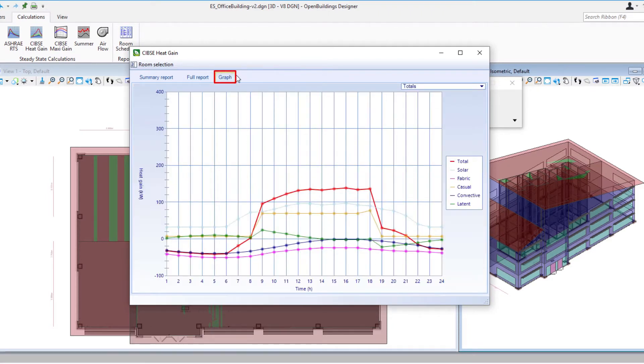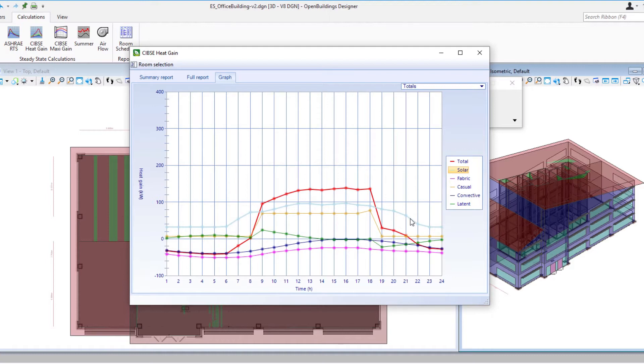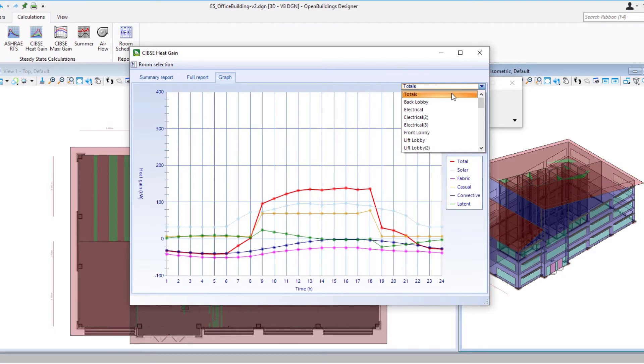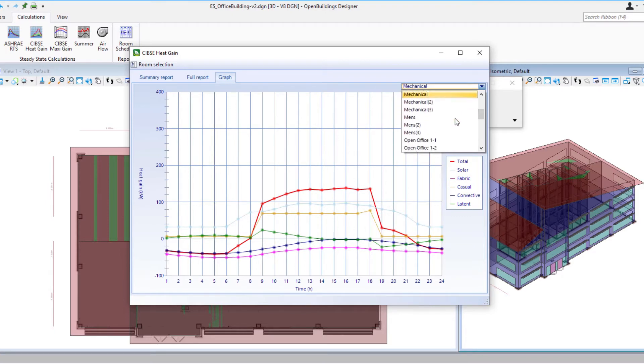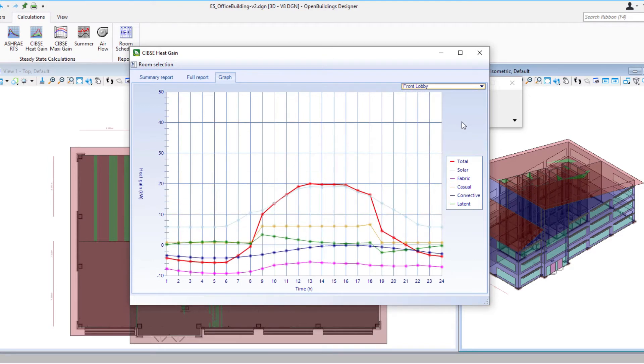And if we go to the graph tab it puts into a graph the different heat gains and we can see for instance that our solar heat gain is the greatest on our graph. Now that's for the total project here. We can also look at it room by room. So for instance I could look at the front lobby and see where the heat gain is coming from. Again it's that solar load that is the greatest.